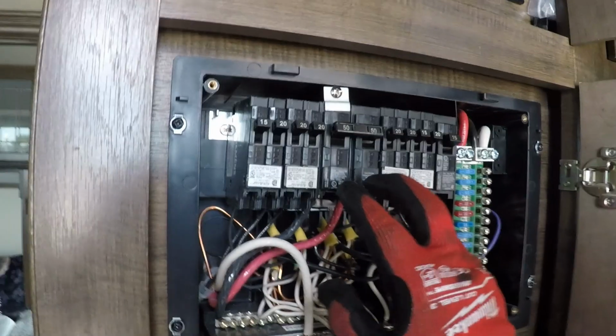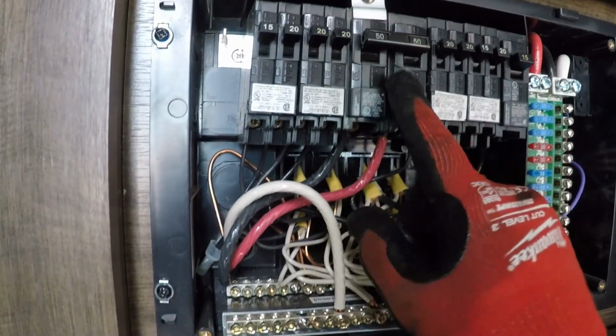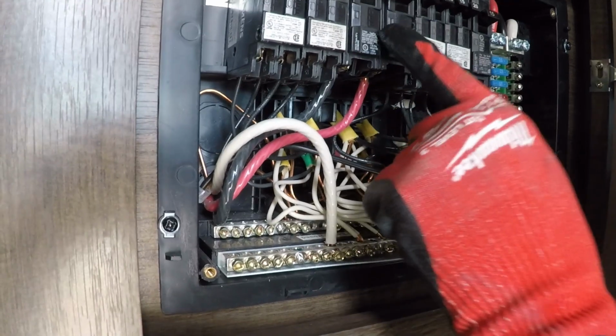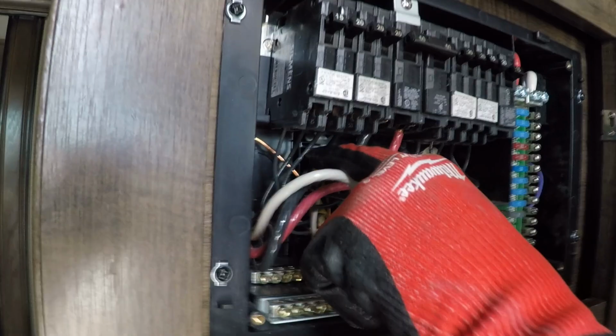We shut down power next morning, making sure the batteries and inverters were off as well, and opened the panel, removed the face so as to access the breakers. Now those main wires coming in are thick and very stiff, so manipulating them is challenging. What we worry about right now is this double and this tandem, because these are the two that tend to be getting the hottest. You notice all the power that's coming into the double pole, and the tandem has got the smaller ones here.